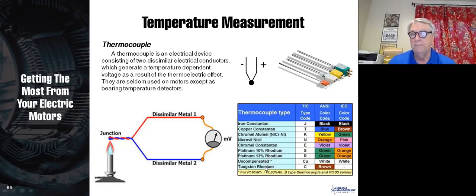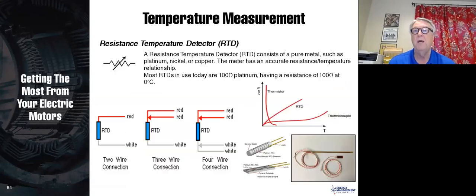We see a type J thermocouple is probably the most common, the iron constantan, but the type K is not unusual, and you really could see any of those things. Now, if you're going to use this, your wiring has to be the same metal as the thermocouple, and you have to have a special thermocouple input on whatever is detecting your temperature. In large motors, this is the most common way to go, and this is a great way to go.